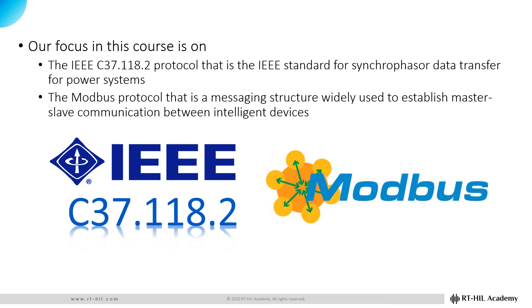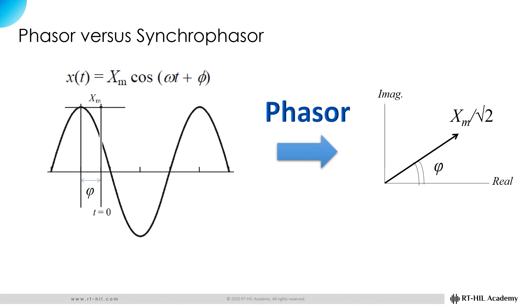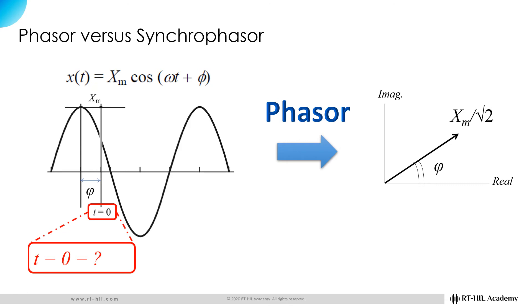Before talking about these two protocols, let's quickly review the definition of synchrophasor and the device that produces it, which is the phasor measurement unit, or PMU. A phasor is the complex number representation of a sinusoidally varying signal. The angle of the phasor, phi, depends on the point at which the signal starts at the beginning of time. The coordinated universal time, or UTC, embedded in GPS signals, can be used to synchronize measured electrical voltage and current waveforms. This synchronization results in a synchronized phasor, or synchrophasor. This process is performed by a device called a phasor measurement unit, or PMU.